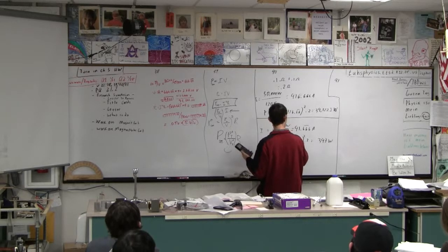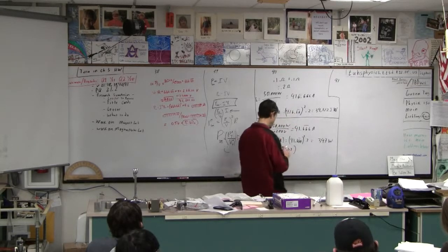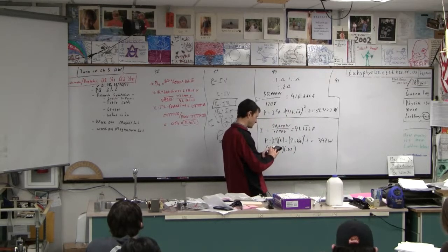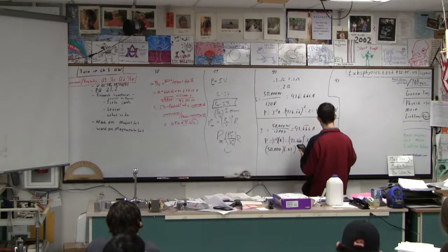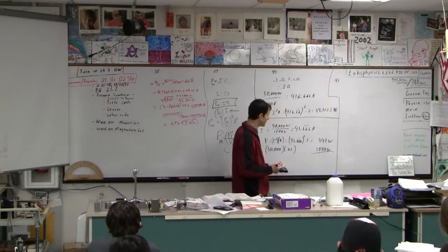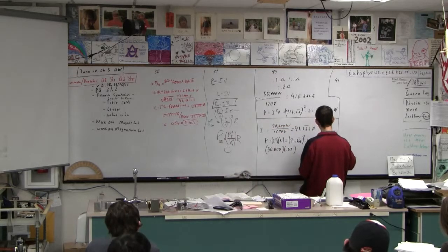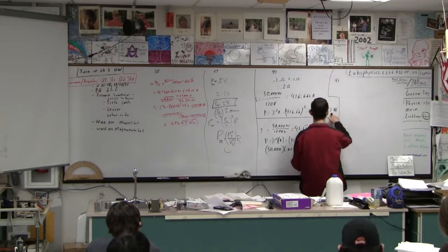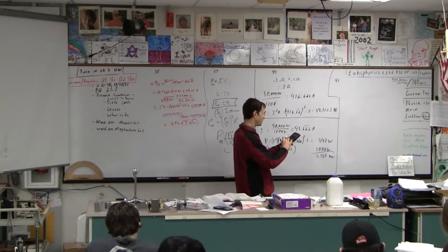So I'm going to say that we also lose 50 kilowatts times 0.02, so that's 2%, which is, of course, 1,000 watts, right? Which is kind of funny. We lose more in the transformers than we lose with I squared R. I wonder if that's always true. And if I add these up, I get that we lose 1.347 kilowatts, right? And then if we subtract the two, right, so that plus 347 is that.